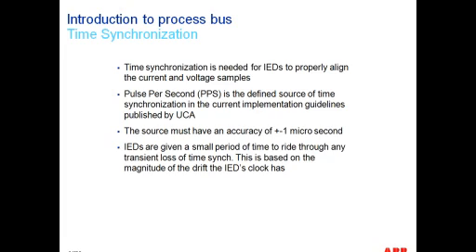So what that means is that if an IED transiently loses its time synchronization, there's a time sync flag that can be set to false or to true, and if it's set to false, obviously the sample is disregarded. But if a merging unit, for example, loses time synchronization, that merging unit is allowed to continue to transmit its samples for a certain amount of time. And that set amount of time is based on the magnitude of the drift of the clock of the merging unit.